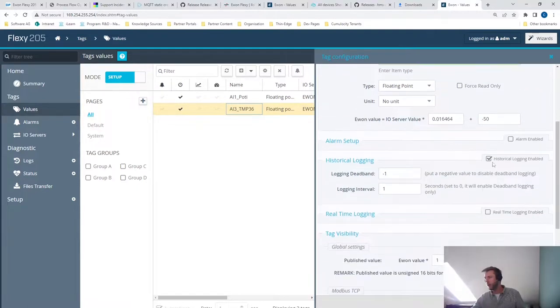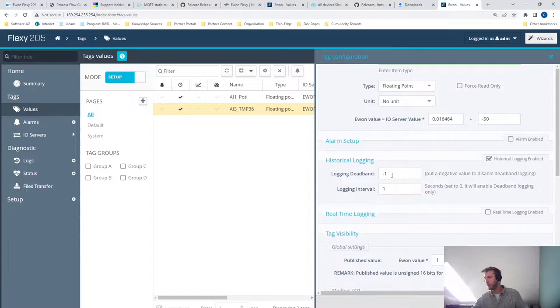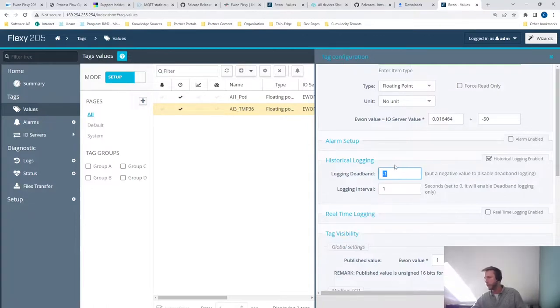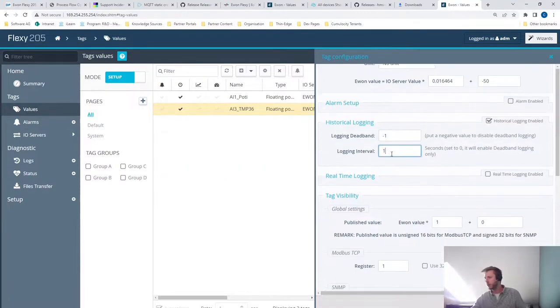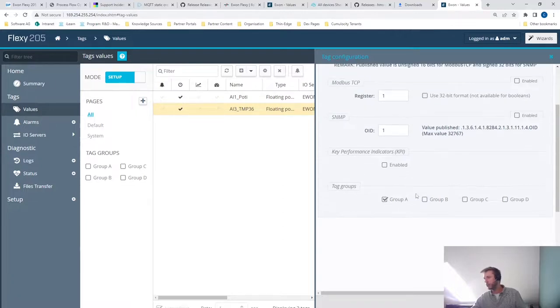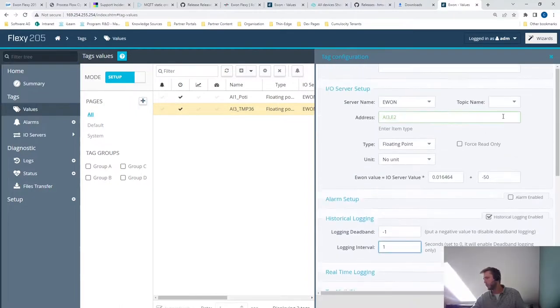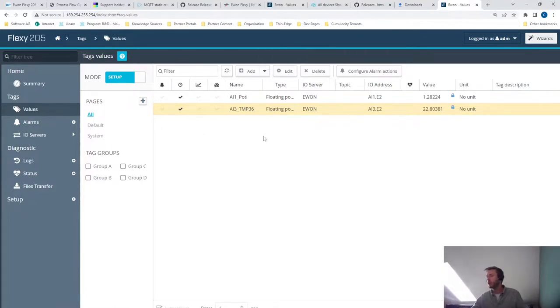And in order for the data to flow to Cumulocity, you need to enable the historical logging. And by this, you can define the sensitivity of the measurement. So for example, if the measurement is just varying a little bit, you can disregard these changes by selecting a value. So it's basically something like a hysteresis and you can select the logging interval. I've set it to one second and you have to assign it to either of these groups. These are the requirements for the connector to detect if the measurements should be sent to Cumulocity or not, the historical data logging and the groups.